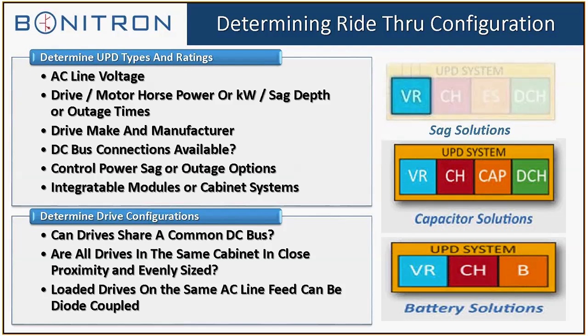And then, depending on integration capabilities of the customer or energy storage sources that they can use, we can provide the integratable modules. If you look over on the right, each of the different colored blocks represents a module within each of the UPD systems. As I said, single unit for sags, and we add energy storage, a charger, and a discharger for the ultracaps. Because ultracaps can take up to 8 hours to bleed off, and you may have to get into the cabinet in a hurry, the discharger is a critical piece of equipment for ultracapacitor systems. For batteries, all we need is a voltage regulator, charger, and the battery.